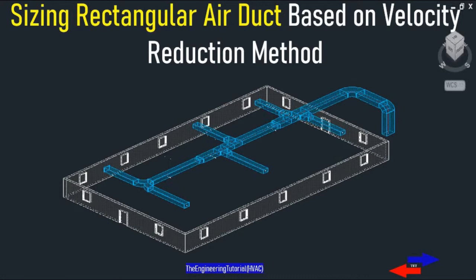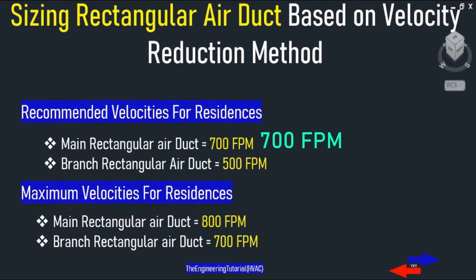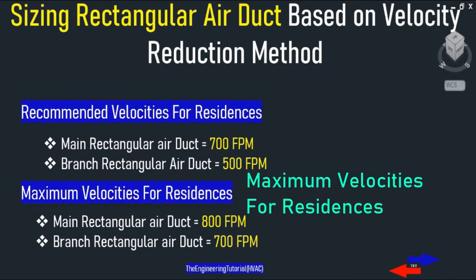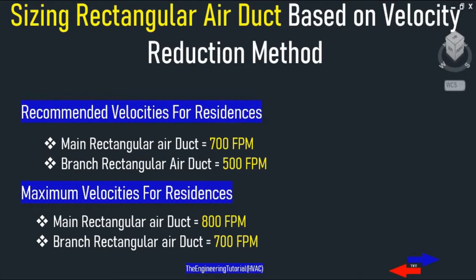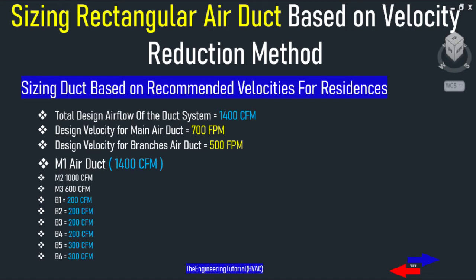The recommended velocities for residential main rectangular air duct is 700 FPM and 500 FPM for branch ducts. The maximum velocities for residential main rectangular air duct is 800 FPM and 700 FPM for branch ducts.